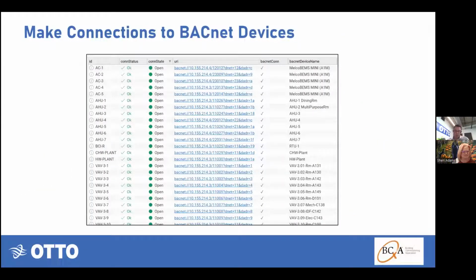Then what do we do? We make connections to all the devices. Every BACnet control system that gets installed has an address for every controller. It doesn't matter whether it's an IP controller or an MSTP controller downstream of a floor panel or something—it has a BACnet address. That's all we need in order to make a connection.